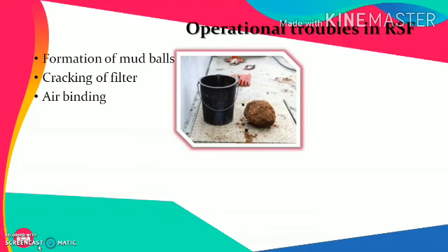So formation of mud ball happens if we are not cleaning the media appropriately. Because of the inappropriate cleaning, the mud starts accumulating in the voids of the filter and then it starts increasing in size, and after a number of days it may increase its size as shown in the figure. It may even trap a good amount of filter media in it and will form a very large mud ball which is then very difficult to wash or to break.